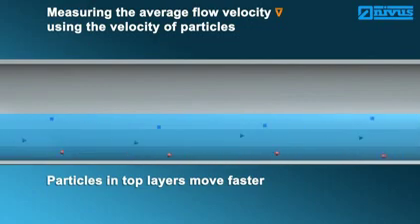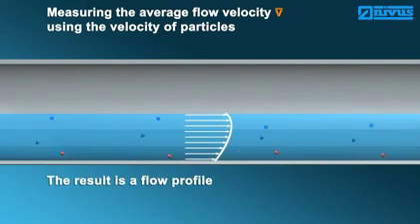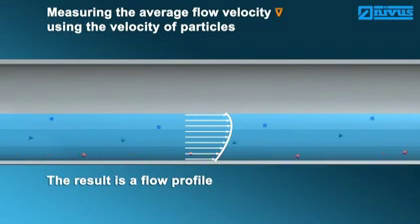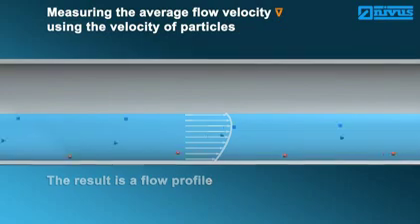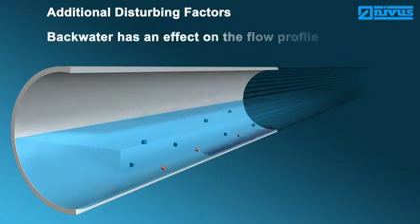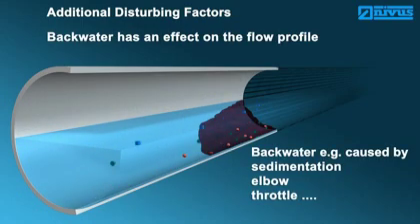From this, a so-called flow profile can be obtained. This profile depicts the flow velocities related to the levels. Miscellaneous factors affect this flow profile, disturbing free discharge or may result in the formation of backwater. Such disturbing factors may be pipe roughness and varying sedimentation, solid concentration, or influences due to construction such as elbows and throttle equipment.